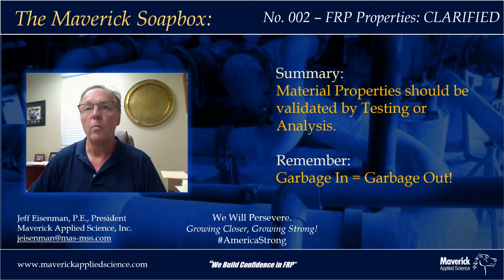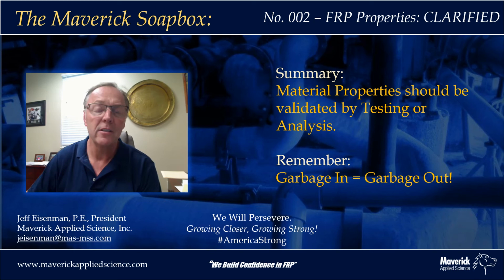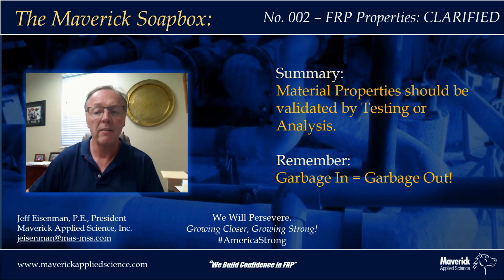Basically what I want to leave you with as a summary is that NM2 requires piping manufacturers to develop these properties. They should be validated by testing or by analysis if necessary. So as an owner, you should be asking for verification of these properties. Remember, garbage in, garbage out. If you don't have that verification, how do you really know what you have?